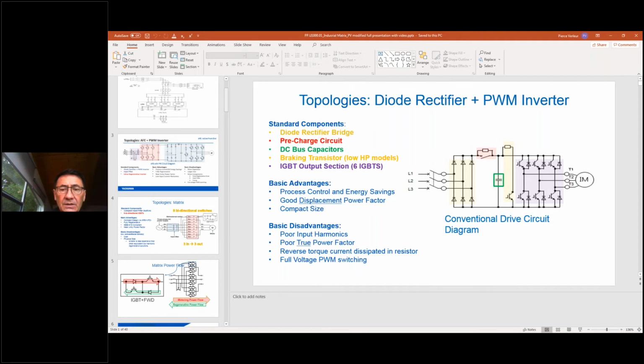The VFD used instead of the contactor gives variable speed capability, therefore the ability to monitor and maintain pressure, flow, tank level, what have you, but damages the submersible pump to the point where it doesn't last as long as it should. Two points of damage: one, voltage spiking from the output of the VFD; two, the harmonics on the output waveform. We're talking output waveform here, not input waveform, but harmonics being defined the same way, the distortion of the sine wave shape.